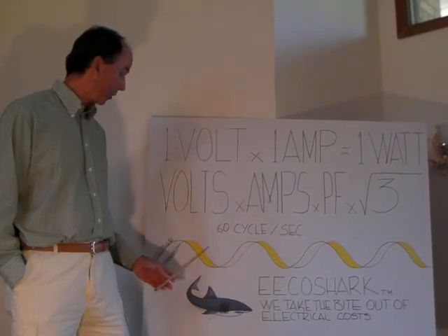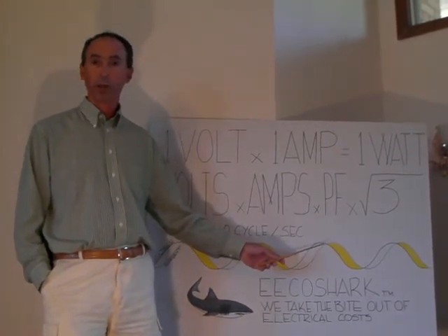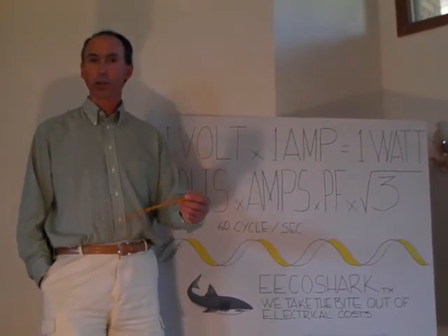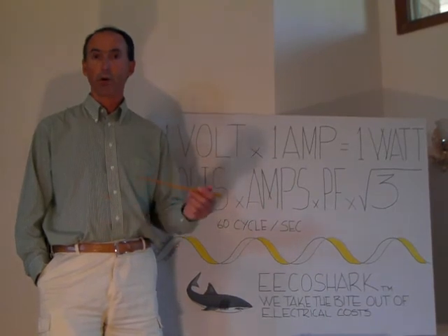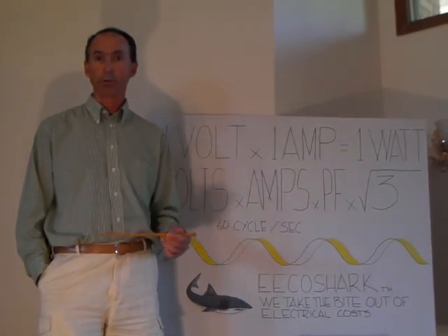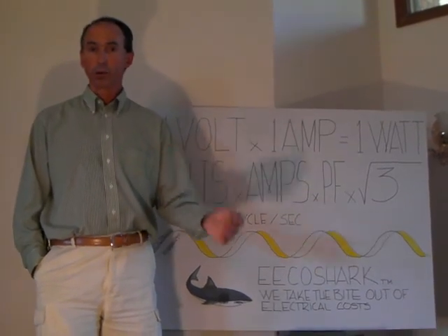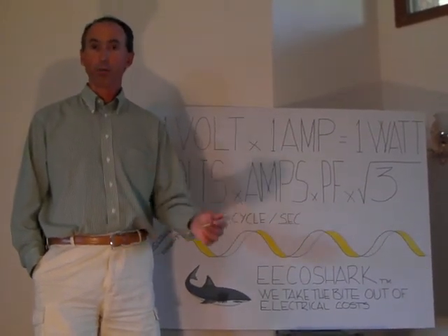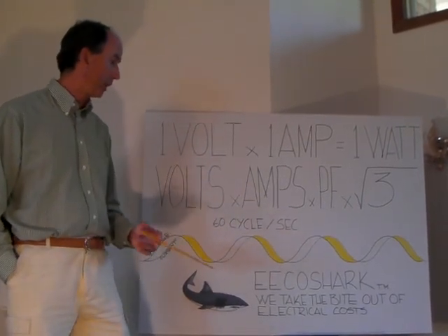We also increased the power factor efficiency much closer to unity at something in the neighborhood of 16% increase. That's what we're seeing on average over electric motors that we've tested that include air handler motors, centrifugal chiller drive motors, feed water pump motors, this sort of thing. These are typical applications for the EECOShark.